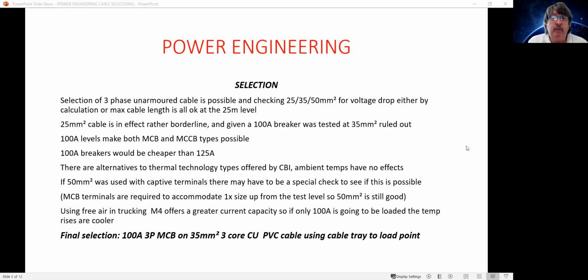At 100 amps, we have other selections here, because we could have a miniature circuit breaker and we could have a molded case circuit breaker. We could say that the 100 amp would be cheaper than a 125. If you have a look on there, you could see that possibly a circuit breaker in the 125 amp class could be specified. A 100 amp circuit breaker would be cheaper than the 125.